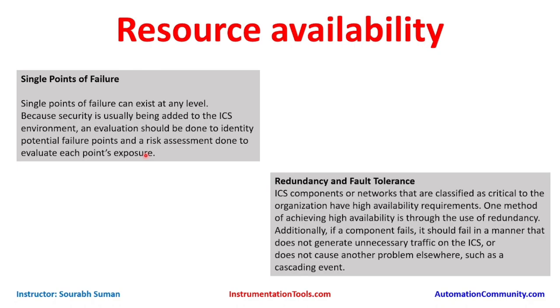The best method to find all single points of failure is to conduct a risk assessment. Based on the findings, we need to pinpoint all points of exposure and check the cost-versus-impact analysis — what will happen if we do not improve the redundancy of this solution, and what could be the impact in terms of financial, safety, health, and reputation. Once the risk assessment is done, we need to prioritize the most impacted single point failures and improve them.